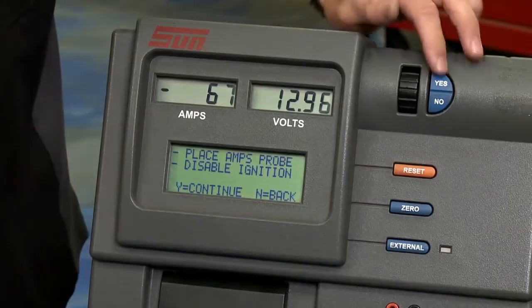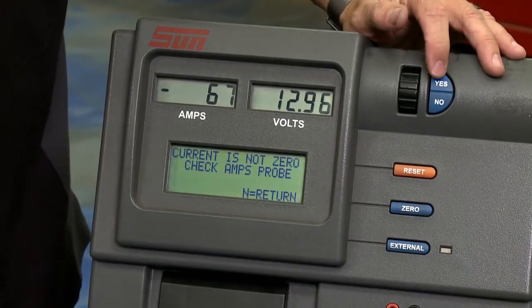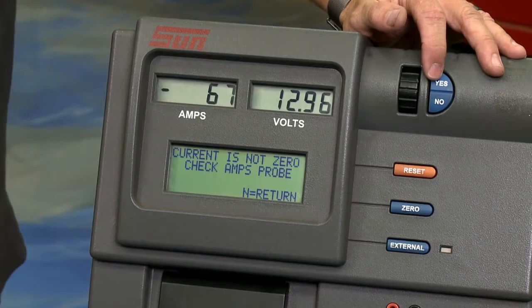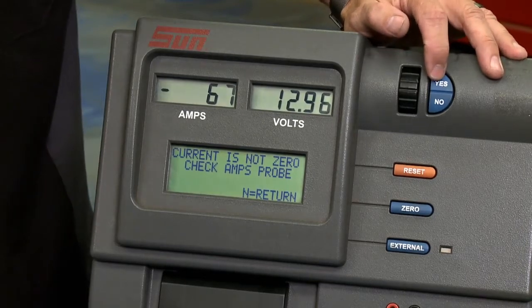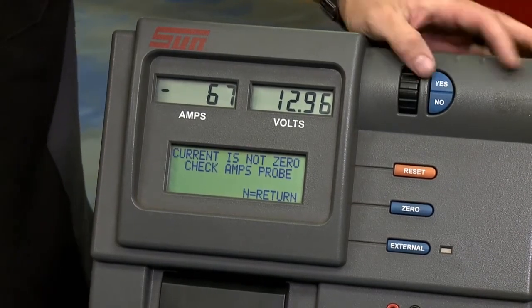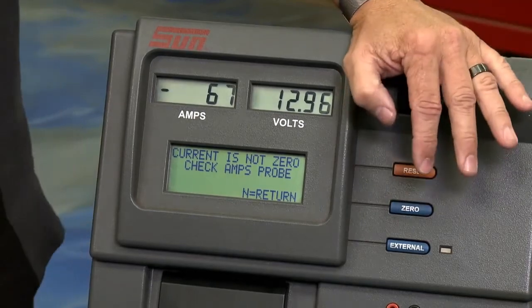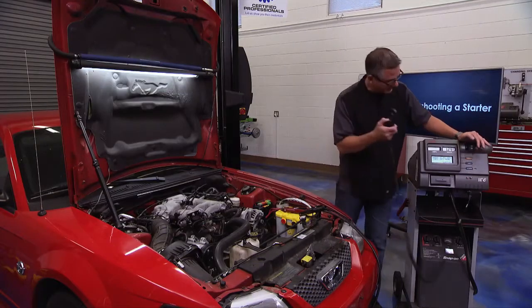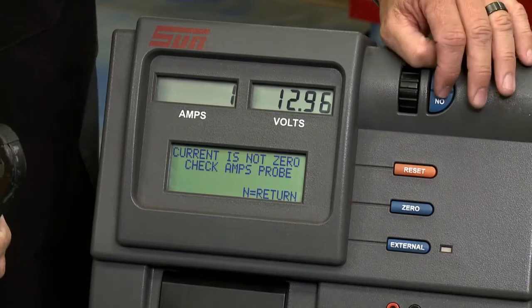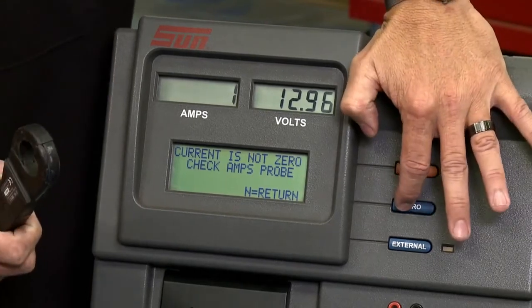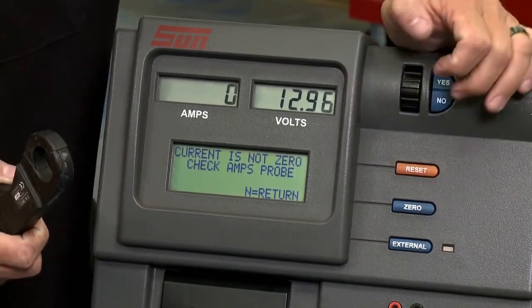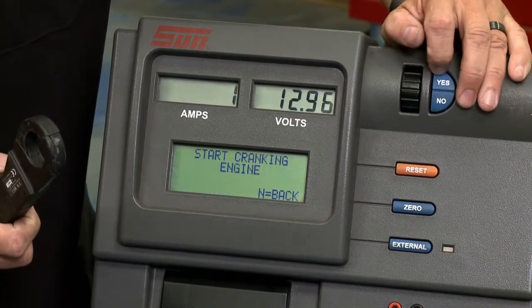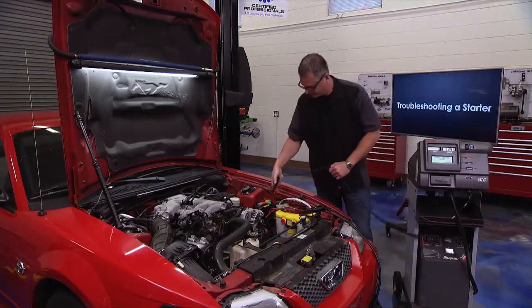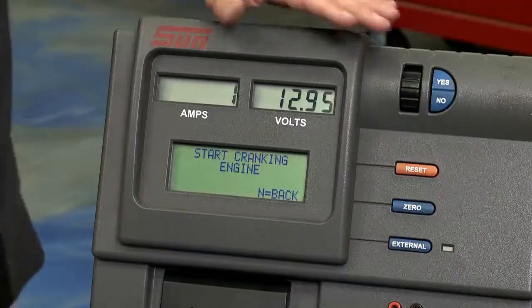Now what I do, I say yes to that. And when I say yes to that, it says go ahead and zero it and put it on. I put the probe on so we're ready to go, hit enter on that one. It wants me to zero it, so I'm going to pull it back off, which is a good idea. Zero it, hit zero. And when I zero the probe, now we can go ahead and put it back on - it's just zeroing it internally.